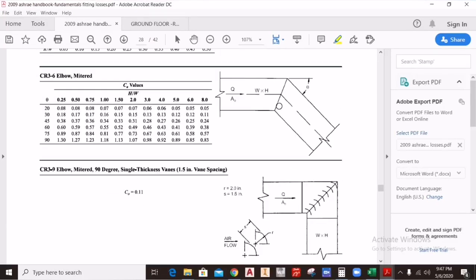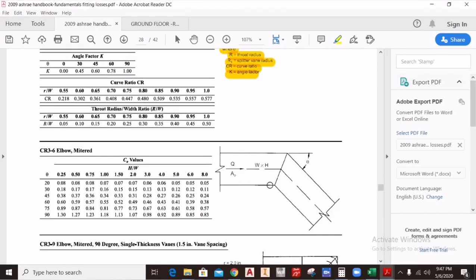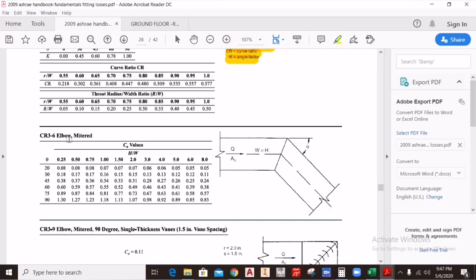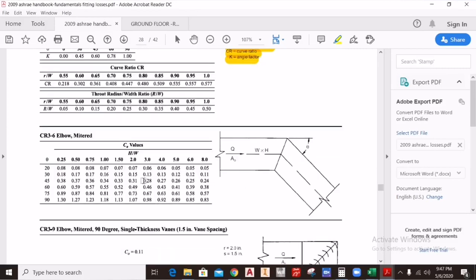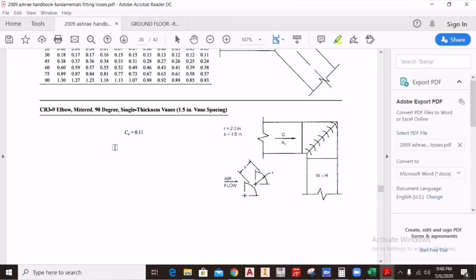For the volume control damper, the basic criteria are the same. For a mitered elbow, C0 is your direct fitting loss — you do not need to calculate Cp here. You just calculate C0 directly using h/w and the angle of the duct. For example, if you are using a 45-degree angle and h/w = 2, C0 = 0.31. Enter 0.31 directly into the Excel sheet and you will get the external static pressure.